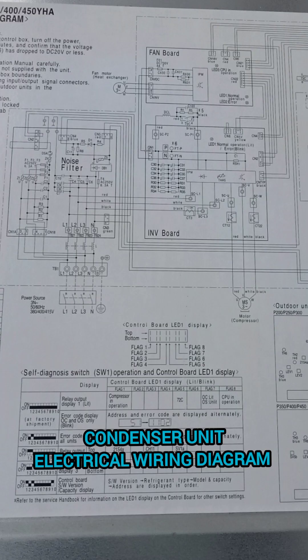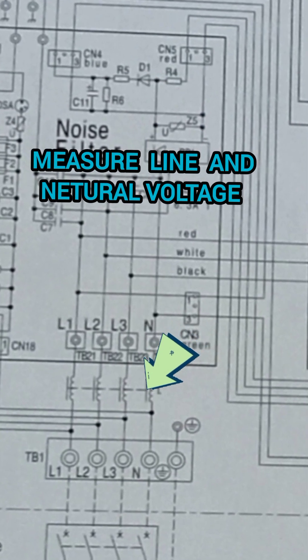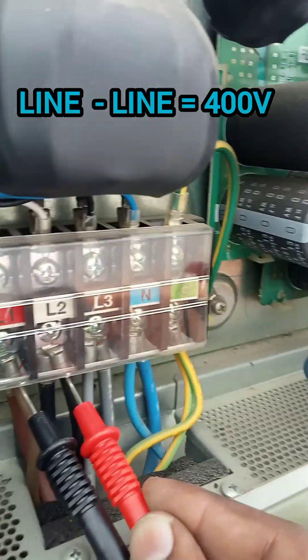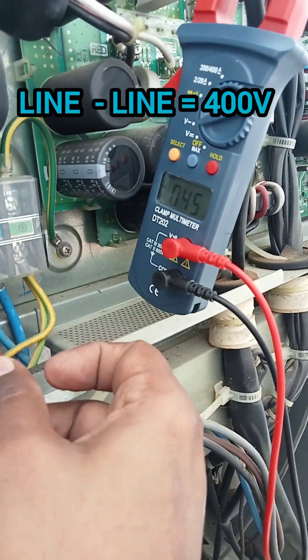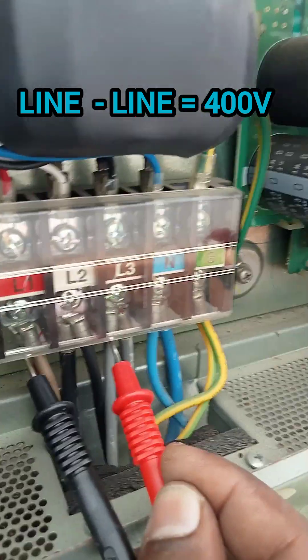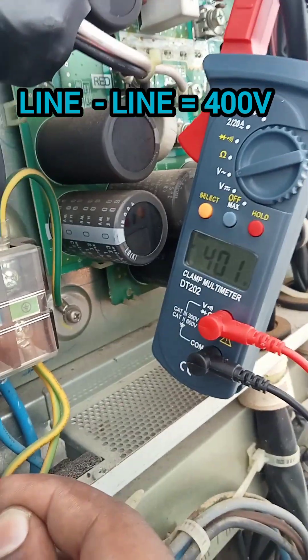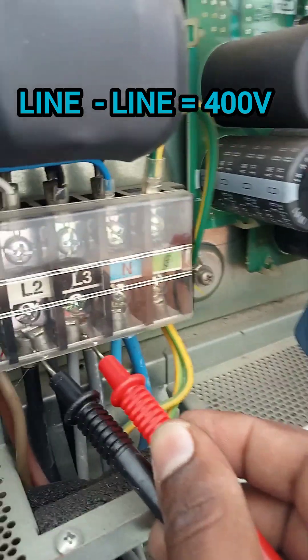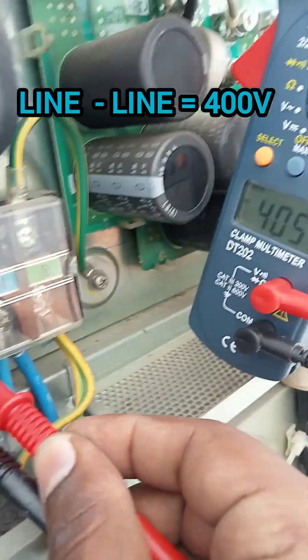We need to double confirm the main power supply — 400 volt line-to-line and 230 volt line-to-neutral. We check line-to-line L1 to L2 at 400 volts, going through all three phases one by one, then checking the 230 volt line-to-neutral as well.